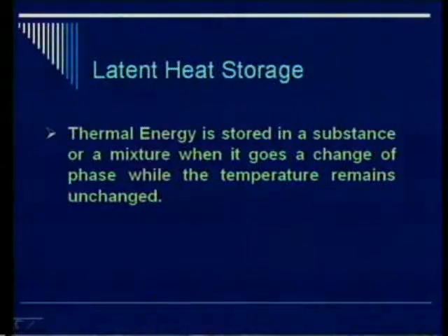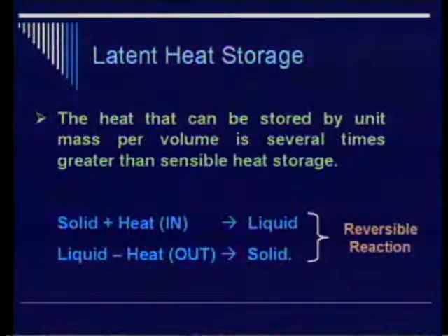Now we will go to the next energy capturing method, that is the latent heat system. Now let us see the slide. In latent heat storage, thermal energy is stored in a substance or a mixture when it undergoes a change of phase while the temperature remains unchanged. The heat that can be stored per unit mass or volume is several times greater than sensible heat storage.